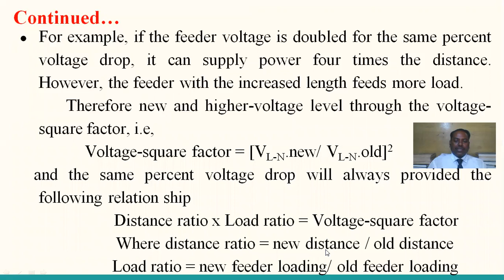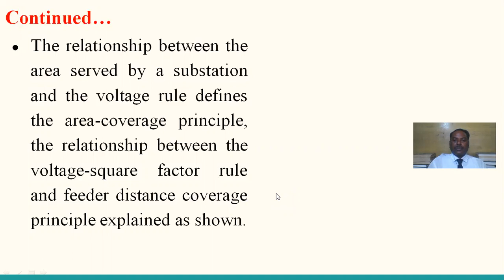Therefore, increasing or decreasing the voltage will change the loading as well as the area coverage. So from this, the voltage square factor is the new increased level by the old level, where distance ratio is new distance by old distance, and load ratio is new feeder loading by old feeder loading. Yes, the relationship between the area served by a substation and the voltage rule defines the area coverage principle. The relationship between the voltage square factor rule and the distance coverage principle is explained as shown here.